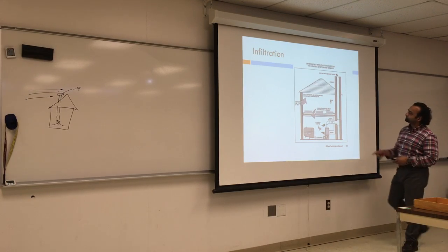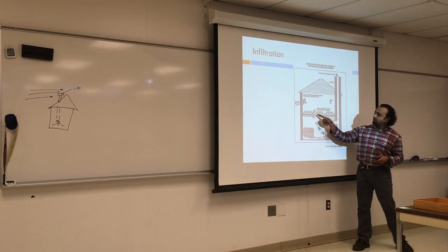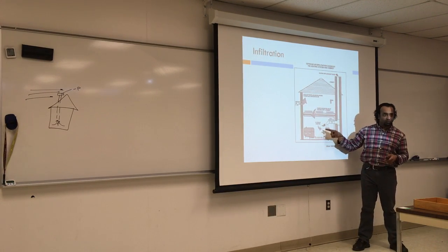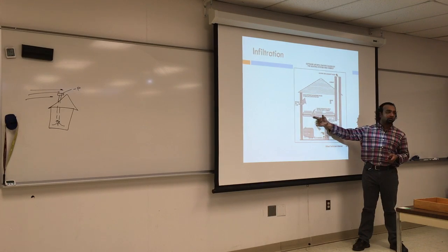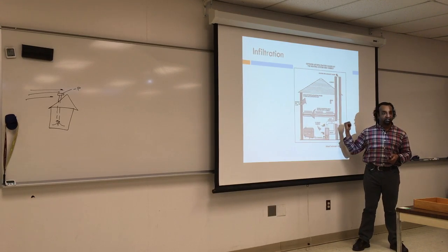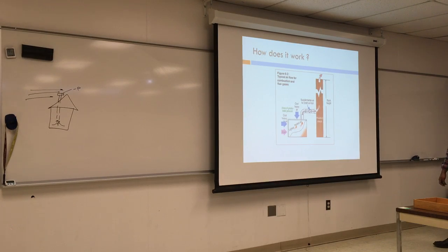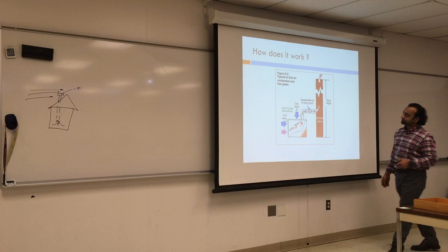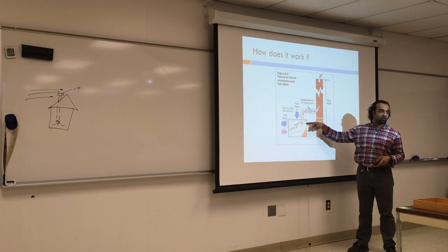So this is again the connection to the house chimney, and how you always have to have some kind of makeup air coming from the house into the basement. Otherwise, this room will run out of air. If you don't have this kind of venting, either a basement door, you might have to make an opening for it, or you have to bring in air from the outside. This is how it works. Again, supplemental air: if you have too much negative pressure here, you want to supplement air from the room, not from the chamber.